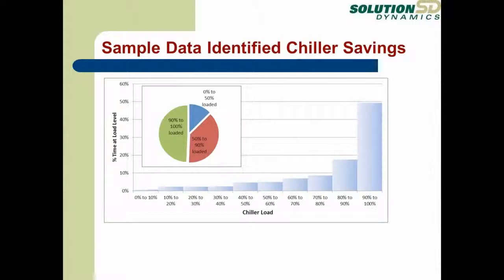And the way that the system was programmed was that they would base load one chiller. Once it got nearly fully loaded, they'd base load another chiller, and so on. So they'd stage up their chillers, and you'd have multiple chillers running at full load, when actually the chiller performance is much better when it's at around 50% to 60% load.